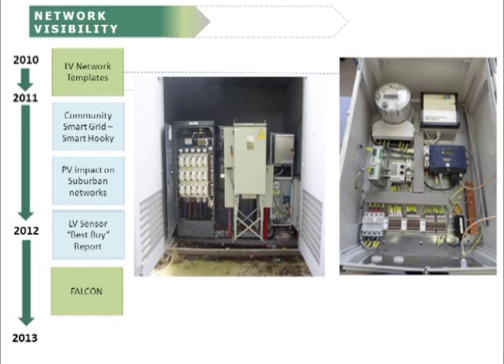Originally we started with a project in South Wales called the LV Network Templates. The plan was to monitor a large number of substations across the South Wales area. We recognised that the existing CTs, the current transformers in the back of the low voltage pillar, behind those white fuse carrier handles in the photograph, were insufficient for the work we needed to do - they weren't accurate enough.